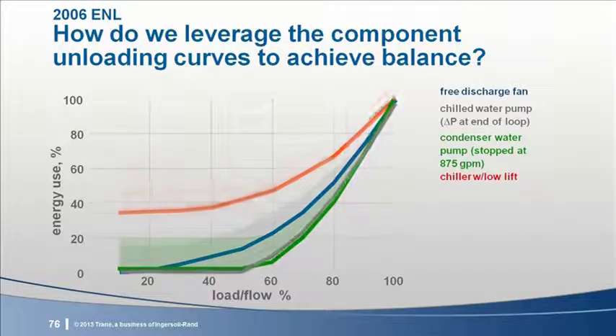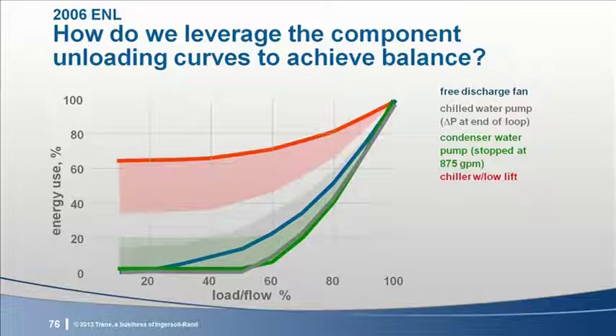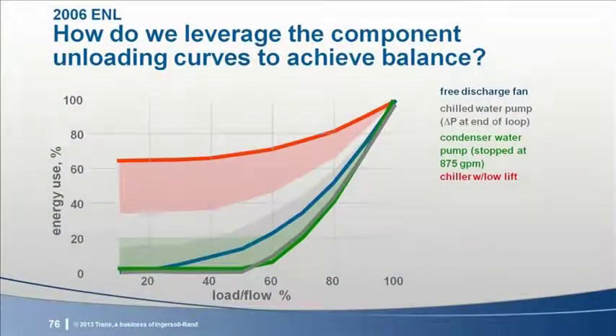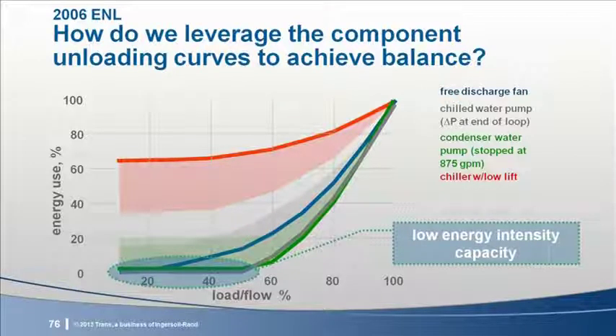The chiller condenser would get a lower flow of warmer water, which would increase the compressor's lift and energy use. Again, the question is, would this lower or raise the system energy use? Mick's earlier analysis had the answer. The system power would go up. In the examples he analyzed, between 5 and 10% again, from a fully optimized system. The chart demonstrates why. This sequence does not take advantage of the greater flow available at very low energy intensities from the fan and pump at the relatively low speeds. This sequence results in a relatively large increase in chiller power use, which overwhelms the minimum fan and pump savings.